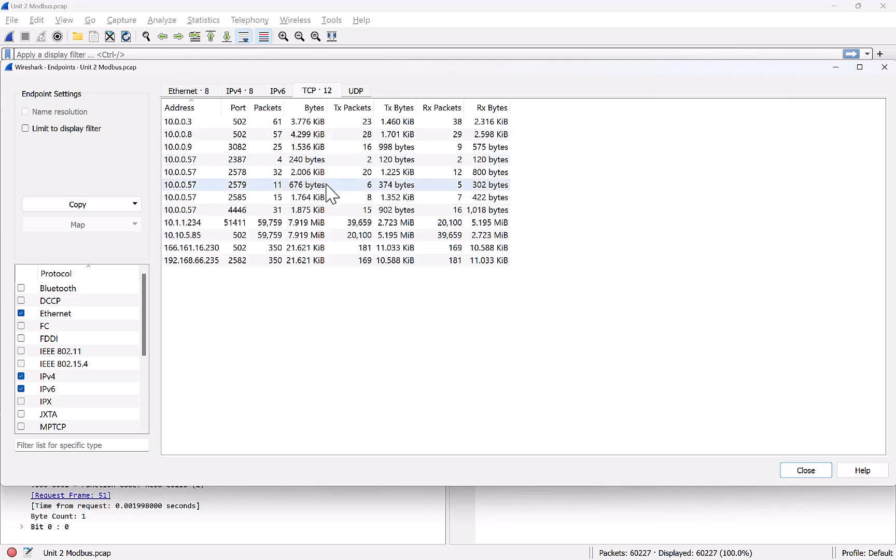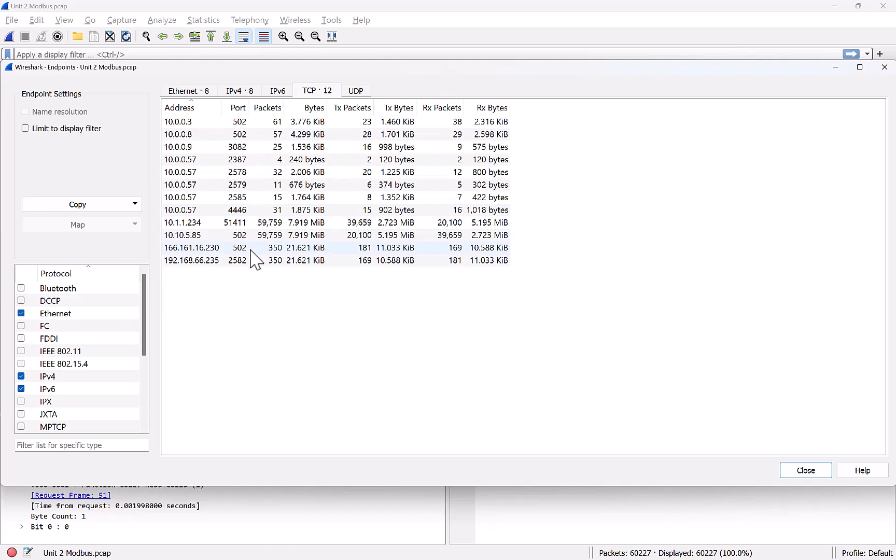So again, this is a way we can look at, based off of, here's 8 IP addresses that we have in the environment. We also looked at, here's the 8 MAC addresses that go with those IP addresses. You can see we don't have any IP version 6, which is completely fine by me. And then we can also see, there's no UDP traffic. We can see there's TCP traffic. And we can also see the ports. So you can see a lot of different ports. The ones that we're usually keen on are those destination ports of TCP 502, which is used for Modbus.